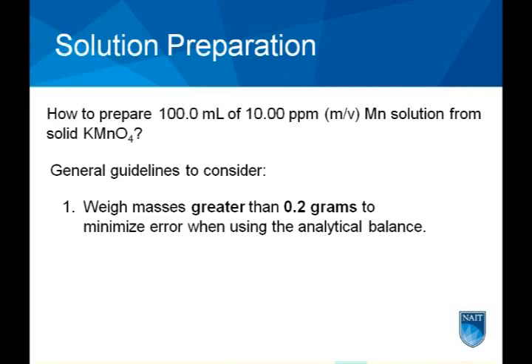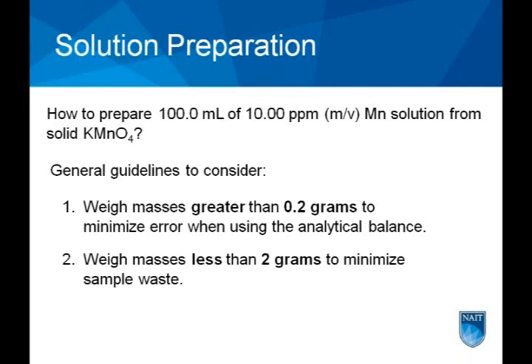Weigh mass greater than 0.2 grams to minimize error when using the analytical balance. Weigh mass less than 2 grams to minimize sample waste.